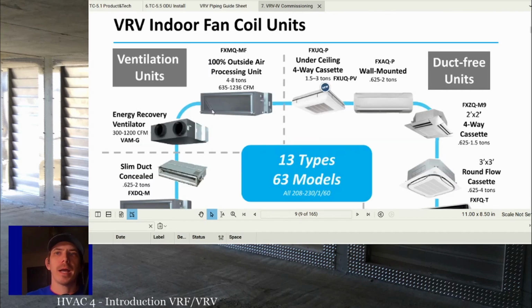And then they have outdoor air units and energy recovery ventilators. These things are becoming more common, but for the most part, most engineers will stay away from using the ventilation units on VRF and use dedicated outdoor air units. It's generally considered better design. I don't know if it's still that way. They've been working towards making these work better, but because of the amount of heating and cooling required to condition outside air as it's coming in, this is generally not an ideal application of VRF technology.